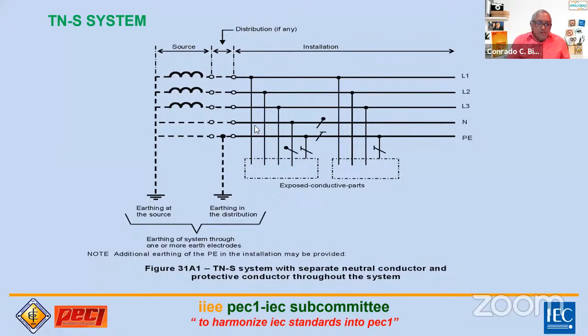Kung makikita mo rito, T and N, naka-earth yung neutral at the source. So you have earthing distribution, ito, then from this one this could be a cable or you can have an MDB, main distribution board, na nandun yung connection niya. Pero kung ang transformer at distribution ay galing sa private, hindi sa utility, it can be considered as part of the installation.